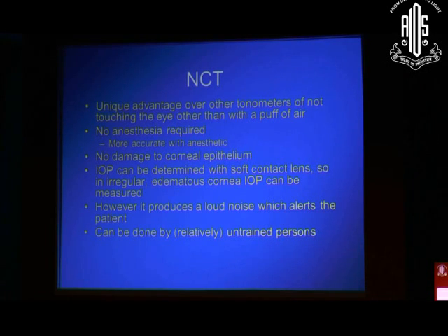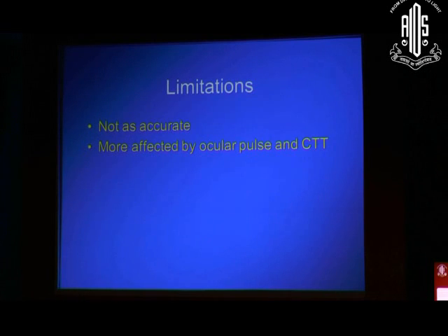It has unique advantages: you can do it without anesthesia, though readings are slightly more reliable if you use anesthesia. Theoretically, you get no damage to the corneal epithelium — however, repeated NCT is known to cause sub-epithelial cysts. Intraocular pressure can be determined over a soft contact lens, which is a huge improvement. It can sometimes be startling to a patient doing it for the first time, so it's sometimes recommended that you discard that first reading. Its limitations are that it's not as accurate as Goldmann Applanation Tonometry, and it's more affected by ocular pulse and central corneal thickness.